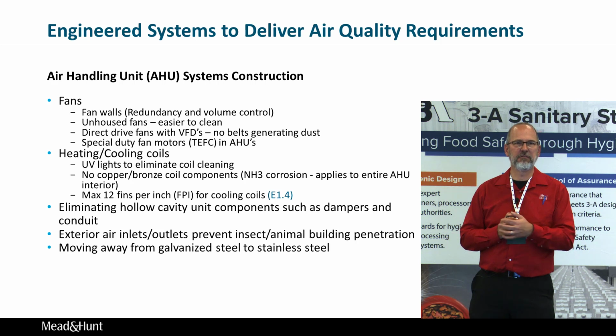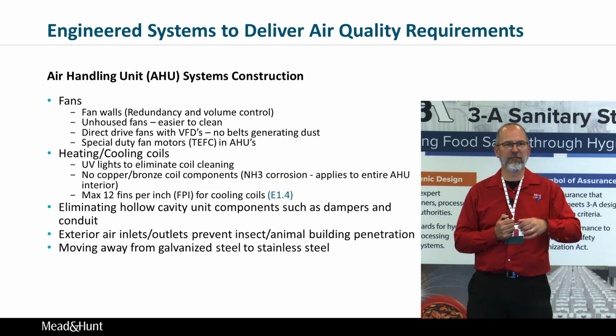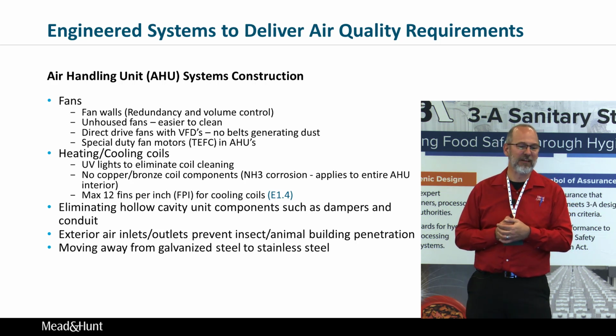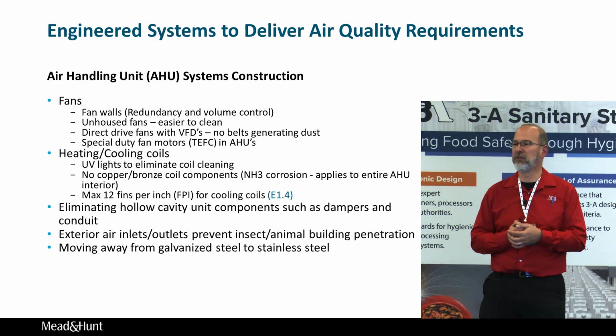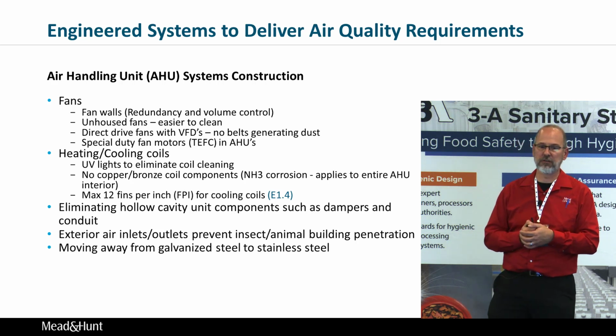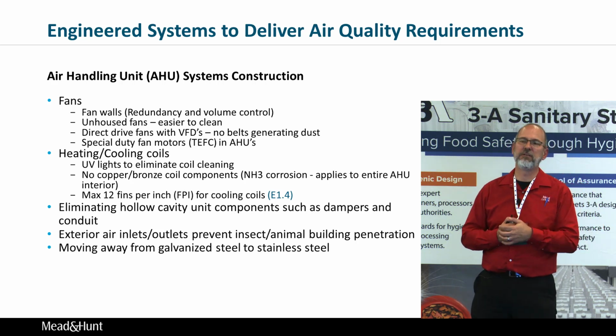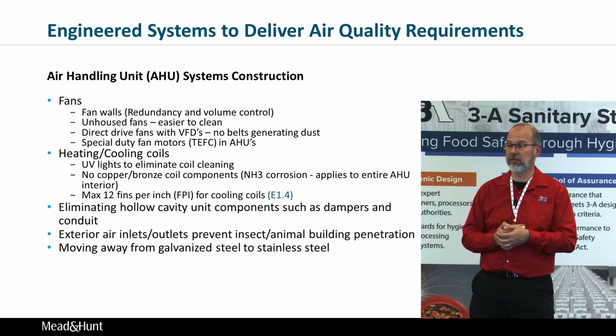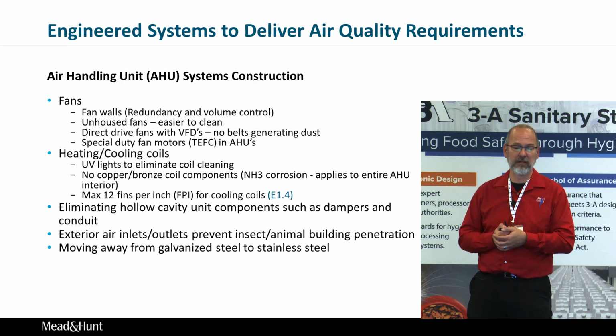They're very effective at, and this gets back to the biofilm discussion right before ours, keeping a cooling coil clean, because that's one of the places in a process air handler that will breed biofilms and bacteria, a cooling coil surface. And if you place a UV bank right downstream of that cooling coil, you can keep it remarkably clean, actually. We've had a lot of experience installing those with good success.